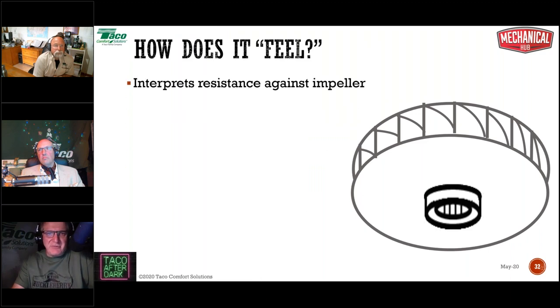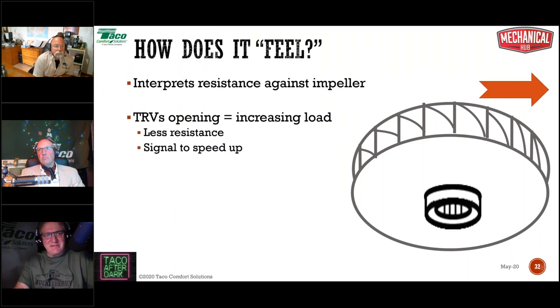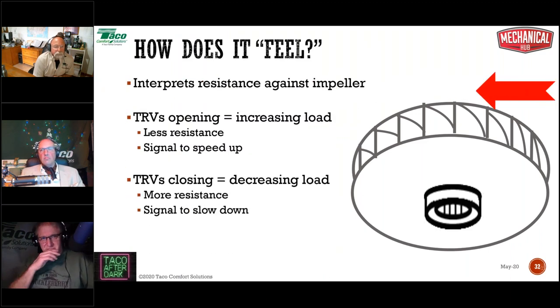All right, how does it feel? Like we said before, it's resistance against the impeller. As TRVs open, the load is going up, there's less resistance against the impeller. That's a signal for the pump to speed up. And as TRVs close, decreasing load, it's vice versa. It goes the other way.